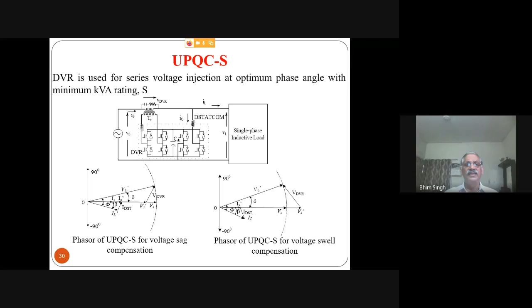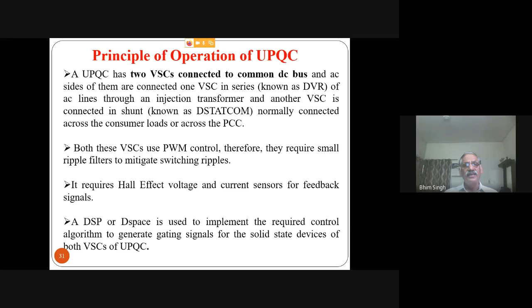Maybe the shunt can be used for harmonic compensation, in the sense that we want to use both voltage source converters up to some extent equally, and to have equal losses, so that their temperature rise is equal and their rating utilization is equal, because they might be of identical rating. So that's basically the concept in the different modes of operation. And the control, I told you, there are plenty of control techniques. When I wrote the book, my students had already implemented all ten classical control techniques.